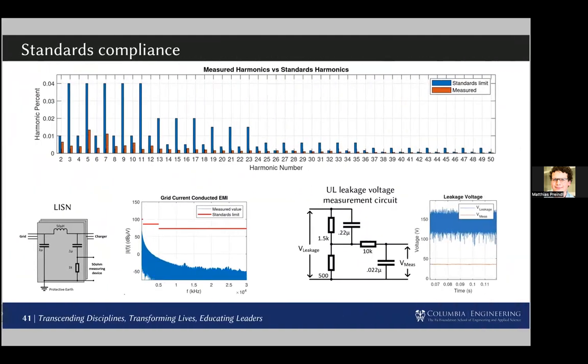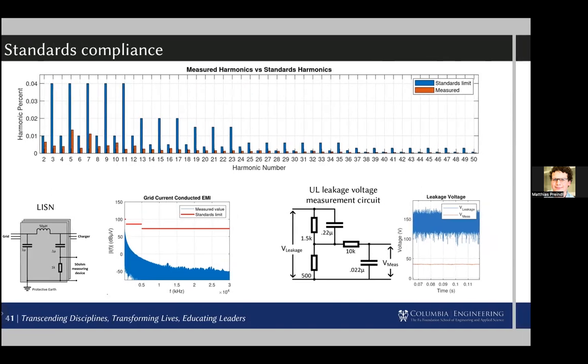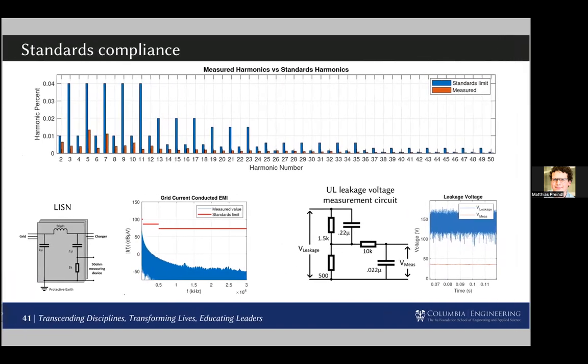The EMI and standards compliance is important. Typically, there are two standards we need to manage when we talk about grid-connected converters. One is the harmonics, up to about harmonic number 50, so 50 times the grid frequency. And then we have the high-frequency components, EMI. For the harmonics, the red are the measured harmonics, the blue are the allowed harmonics by standards. These are experimental measurements. Similarly, we have the EMI measurements, so we need to stay below certain limits outlined by the standards. Similar for the common mode leakages.